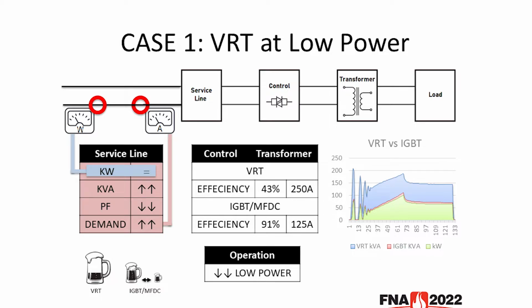An IGBT MFDC power supply is 91% efficient compared to the VRT's 43% efficiency. This means that the IGBT MFDC power supply is passing real power more efficiently. It is also important to note that the IGBT MFDC power supply was sized for the full capacity of the furnace, which means it is also running at 26% full capacity. Going back to the beer mug analogy, a VRT is like a fixed size mug. The less you fill it, the more foam you get. With an IGBT MFDC power supply, the mug grows and shrinks with the cycle, always giving you mostly beer and little foam.